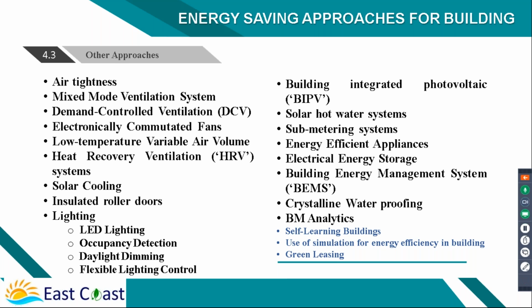Then there's heat recovery ventilation, heat recovery wheels are available. For example, the return air going out may be at around 27 degrees, and outside air might be 30 or 35 degrees. You can use this heat recovery wheel to reduce the incoming fresh air temperature to around 27 or 28 degrees before it enters the system. So heat recovery wheels are also used in buildings.